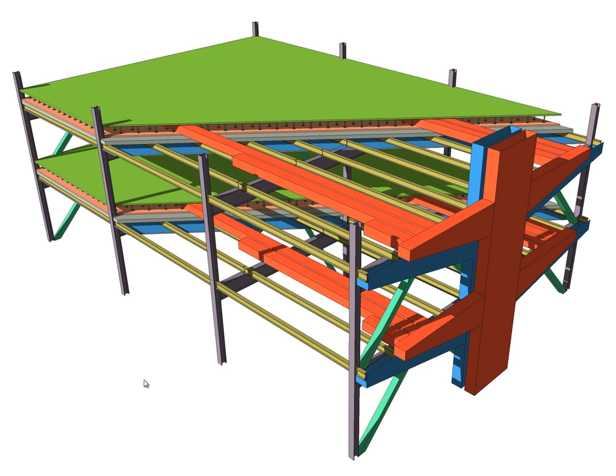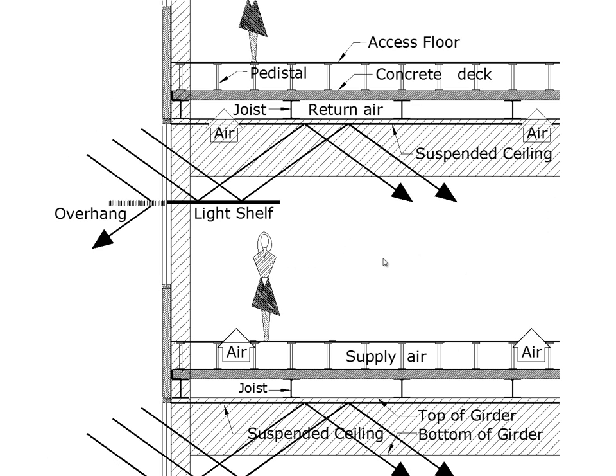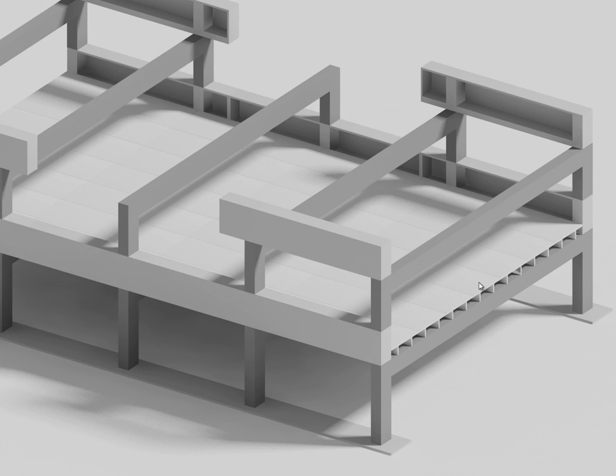In a previous video we talked about a steel system with steel joists that work in composite action with the concrete deck, a series of steel girders running in the north-south direction, a plenum volume under the access floor, and a plenum ceiling where the return air comes back between these steel joists. In that system we were able to reduce the floor sandwich — from the ceiling of the space below to the top surface of the floor above — to something on the order of three foot two or three foot four inches, which is substantially better than the typical five to six feet. We also showed a similar arrangement made from precast elements.